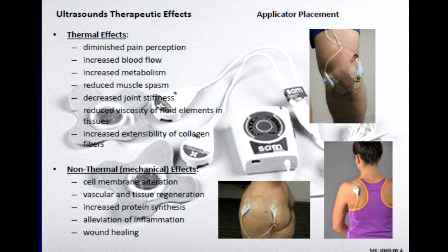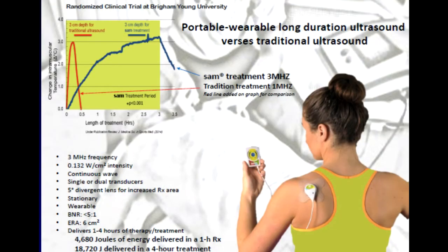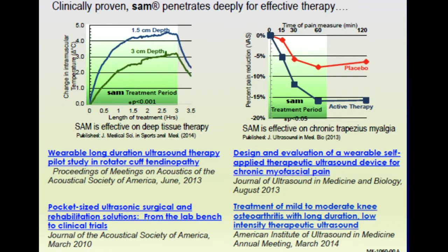There's a graph comparing the SAM unit at three megahertz versus traditional ultrasound at one megahertz. With the SAM device, over a longer duration — two to three hours — you can see significant changes in intramuscular temperature. With a traditional sound head, you get a temperature rise but it's very short-lived, about half an hour. With the SAM device you can sustain that effect for two, three, or four hours at a time, which is a very unique situation.